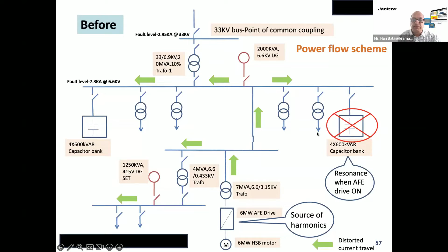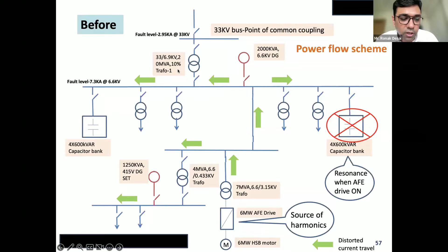The plant power was getting voltage at 33 kV at the input. The symptom was that suddenly this 33 by 6.9 kV transformer, when this drive was first switched on during the commissioning stage, for a fraction of a second started making noise, and the noise value was somewhere around 110 to 120 dB. This was the first symptom observed when the active front-end drive was on. After some time, suddenly the 6.6 kV capacitor bank also started humming and making a tremendous noise, maybe because of a resonance phenomenon.